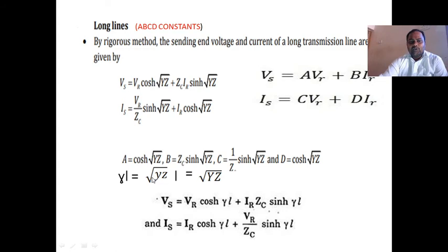If the small admittance is multiplied by the total line length, and the small impedance is multiplied by the total line length, we get capital Y and capital Z. So finally yL is equal to capital Y, zL is equal to capital Z. Small y is the admittance at a particular point only, small z is the impedance at a particular point only.